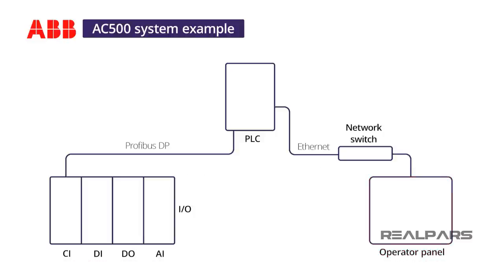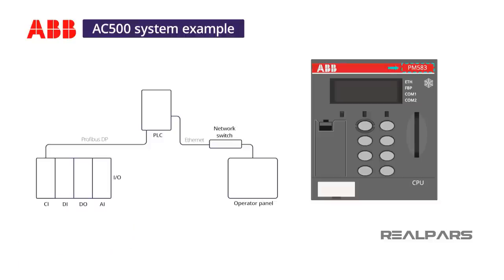I consult the latest ABB PLC automation catalog to learn more about the hardware offered in the AC500 product line and the specifications for each device. First, I select a CPU that will be able to handle the communication interfaces and the small number of I/O points in my system. I choose the PM583 ETH CPU, which comes with 1 MB of memory, one Ethernet port, and two serial ports.